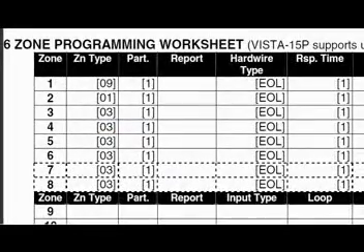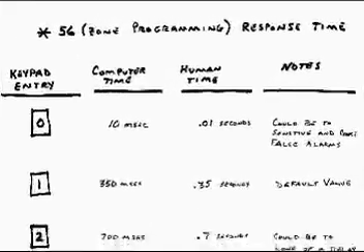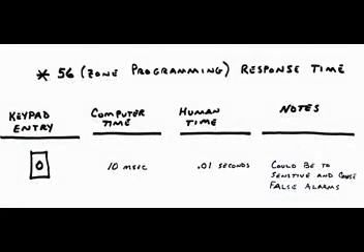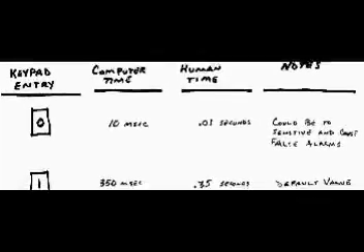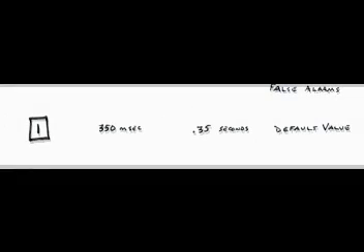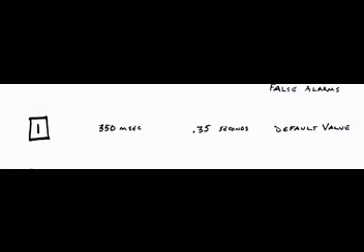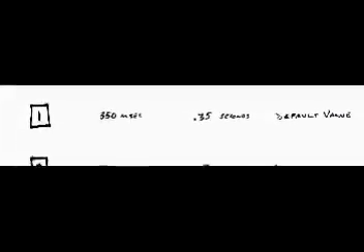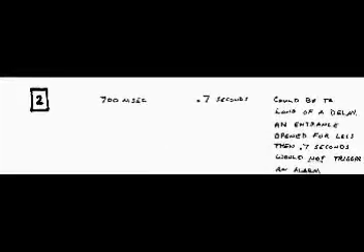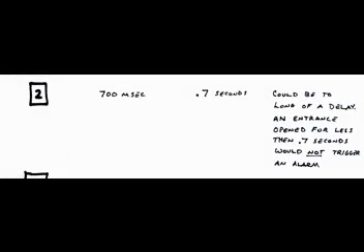The last thing we need to look at is response time — in plain English, how fast will this panel respond to an alarm condition? You have four choices. The quickest response time is entry number zero: 10 milliseconds, or a hundredth of a second. My concern with this setting is that it could cause the alarm panel to be too sensitive and trigger false alarms. The next setting, number one, is also the default: 350 milliseconds — I've never had a problem keeping this setting. Setting number two is 700 milliseconds, almost three quarters of a second. Someone who's really fast could quickly open the door, get through it, and close it without setting the alarm off.